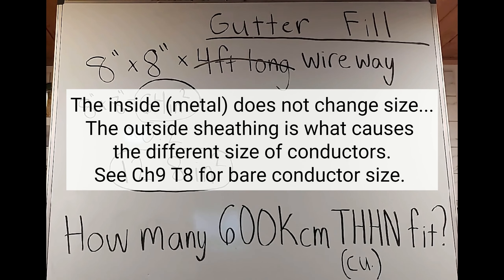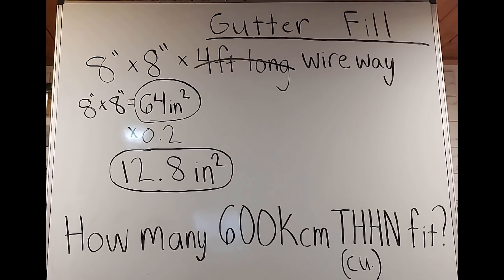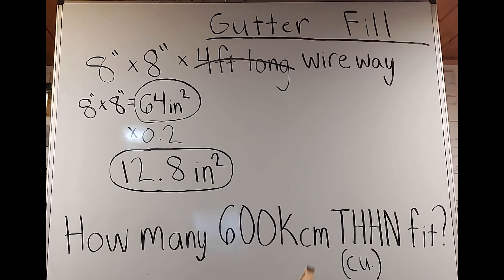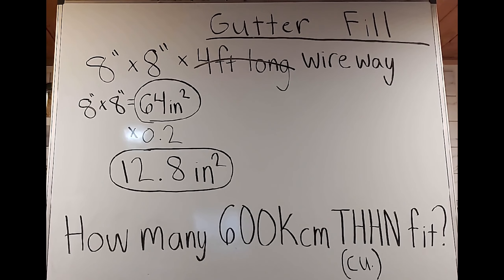What is different is when you go into Table 310.16, the ampacity table, and start to rate the different wires for ampacity — that's where you have a difference between aluminum and copper. The wire type tells you what type of sheathing you're going to be putting on that wire. The ampacity table tells you that when you have a certain wire type with a certain sheathing, how much current can you run through it without the sheathing getting damaged by current flow.